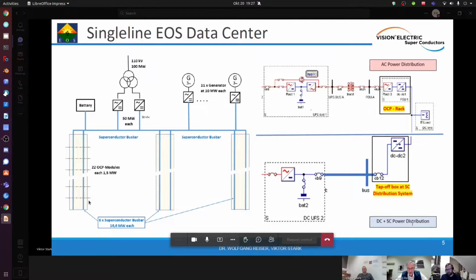Absolutely correct, well recognized. That is one of the big advantages. In most data centers, the problem is not on the supply voltage, the problem is on the ground voltage, and therefore in a lot of cases you normally have double ground wire, double ground cross section, because the ground is in most cases the critical point. Especially in a tier 4 data center you have an A and a B supply, then you normally have a potential difference between A and B, and this is not the case with superconductors.